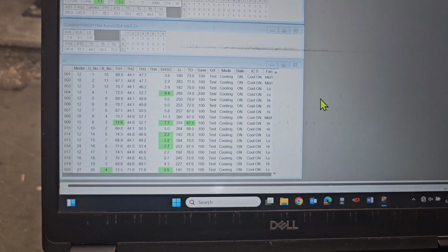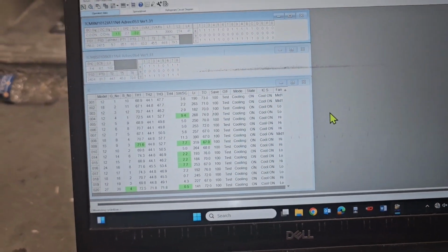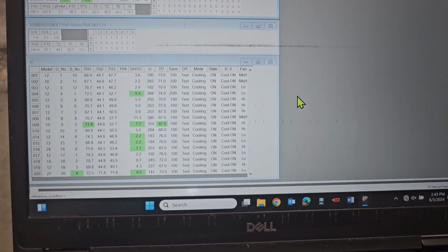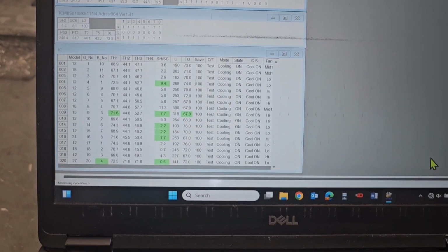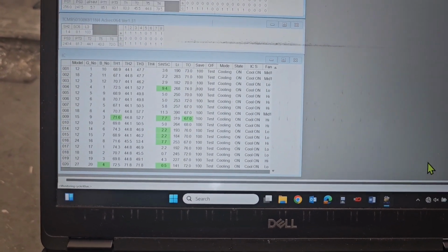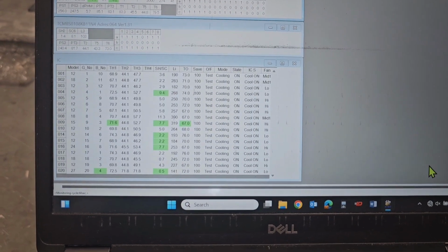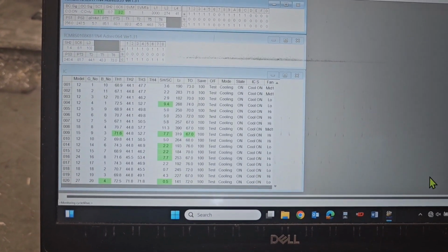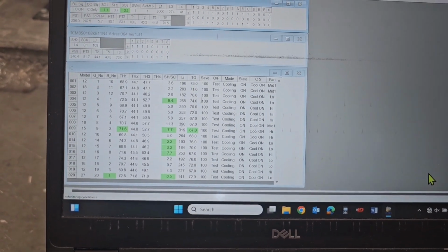The biggest mistake that people make, I have people send me logs on Instagram or other technicians that I work with: put it into one mode and leave it. Do not touch it. Do not change the mode 15 times in an hour. It just makes it impossible to read. Put it all into cooling, put it all into heating, and just leave it alone for an hour and just watch it.